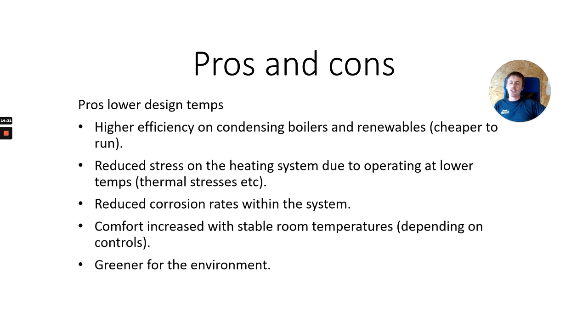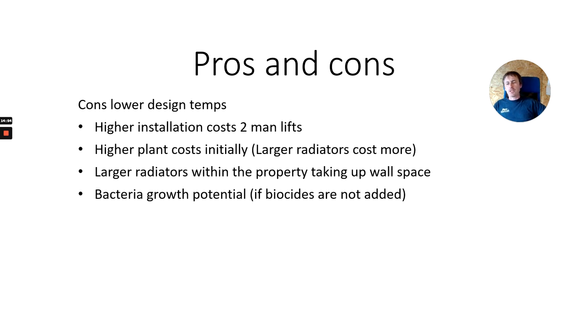Pros of a lower temperature system: higher efficiency on condensing boilers and renewables — cheaper to run; reduced thermal stress on the heating system; reduced corrosion rates; improved comfort with stable room temperatures depending on controls; and it's greener for the environment. Cons: higher installation costs; large radiators may need two-man lifts; higher plant costs initially; larger radiators take up wall space and require a good wall to hang them on; and there's a potential for bacteria growth within the system if water management is not controlled — biocides and VDI 2035 water treatment protocols need to be followed.